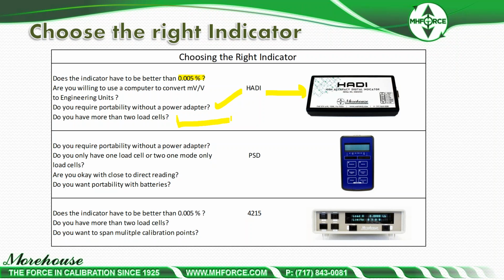My high recommendation is, if you have 3 load cells, to put one of these indicators on each of the load cells. Then guess what? They each have their own indicator. If something goes bad, you can still use the other 2 load cells and only send one back, whether it's the load cell or the indicator. If the indicator goes bad, it's only one load cell you have to have recalibrated. You don't have to worry about the headache of a backup. You only have to worry about that one cell. And if you're running a group, you can easily continue to function with the other load cells. Sometimes if you have enough overlap, you can get by and schedule jobs appropriately. And on most of these, you can have a new calibrated replacement in less than a week if push came to shove.